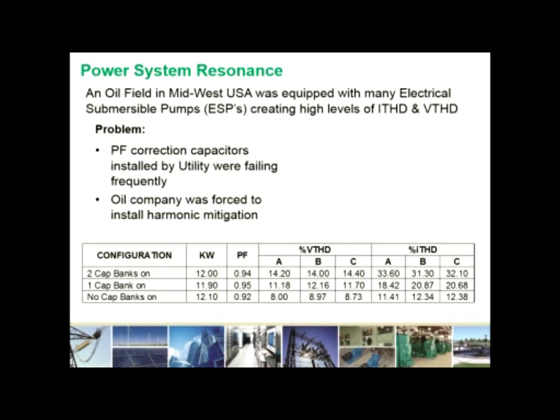But as we were analyzing the situation, we could see the voltage distortion levels, which are shown here, where there were two sets of cap banks on the power factor correction system. The voltage distortion levels were over 14%, which were extremely high. And we've seen high voltage distortion levels, but that was much higher than we would anticipate in this kind of a system. And there were high current distortion levels that were driving that voltage distortion. But we believe that there was some resonance on the system, and so we requested that the utility switch off the capacitors and take measurements as they were switching off the capacitors.